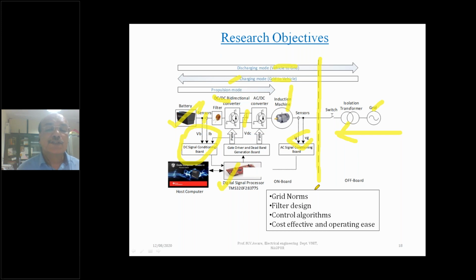But while building this system, we have to keep in mind certain important things. What are grid norms? If you are connecting a system like this, you should not inject any harmonics into the grid. That's one part. Second, it should not load reactive power taken from the grid, so you should always maintain a unity power factor on the grid side.